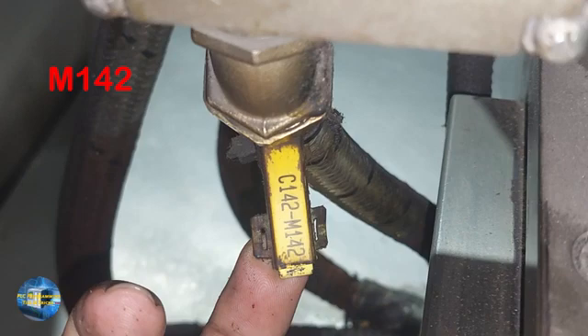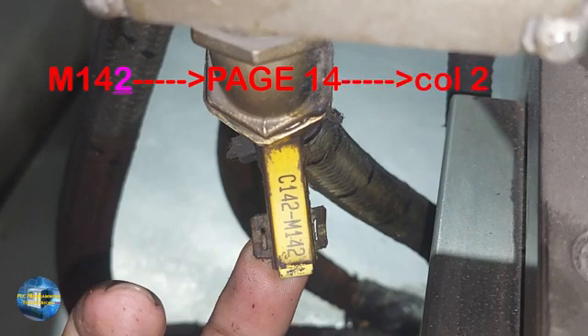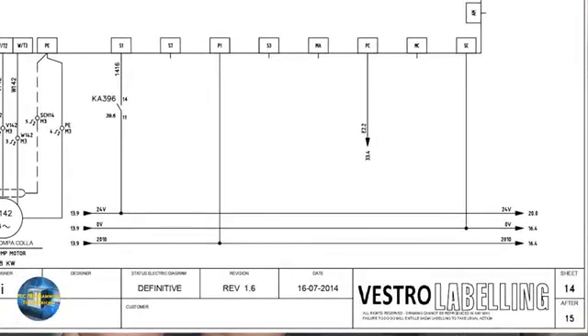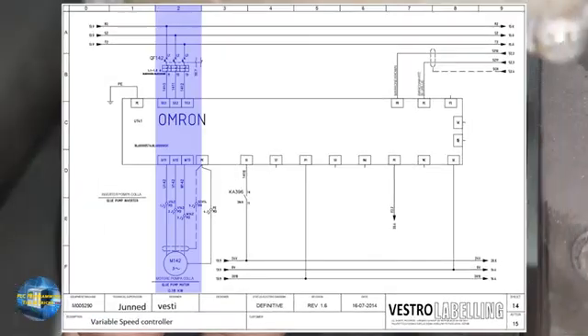If you see, the tag number is 142: the first two digits refer to the sheet number. So this means that this motor is on page number 14. The third number refers to the column number. This means that we have to look in column number 2 of page 14. If you see column 2 of sheet 14, here you can find the motor symbol with tag M142.